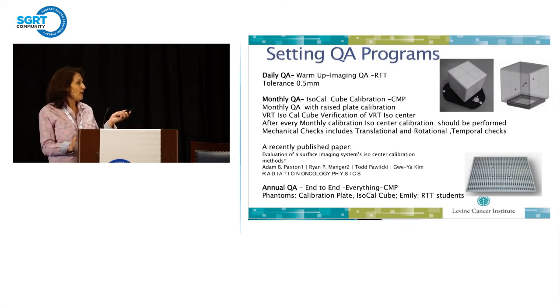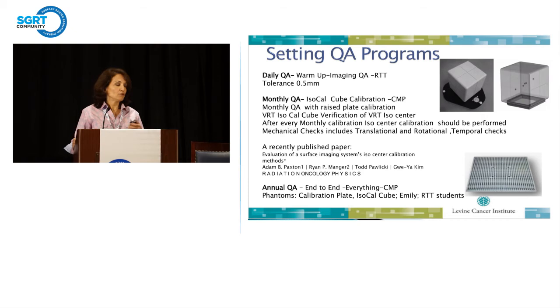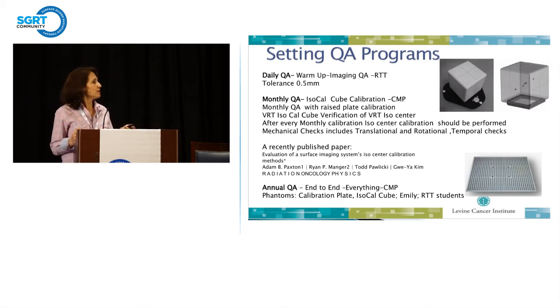And the annual QA is basically end-to-end tasks, meaning from the CT scanning and going through the whole process, how it transfers to the treatment planning system, and then your contours going and doing everything that you do in monthly and translational checks as well.